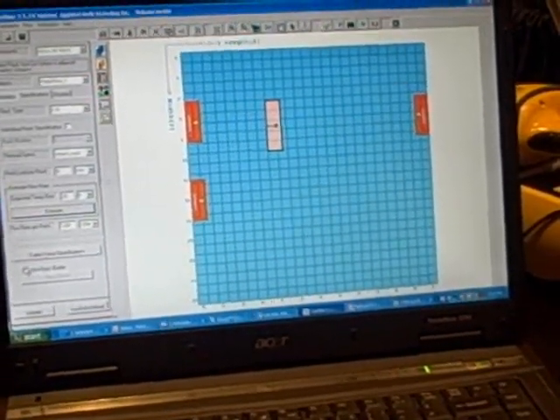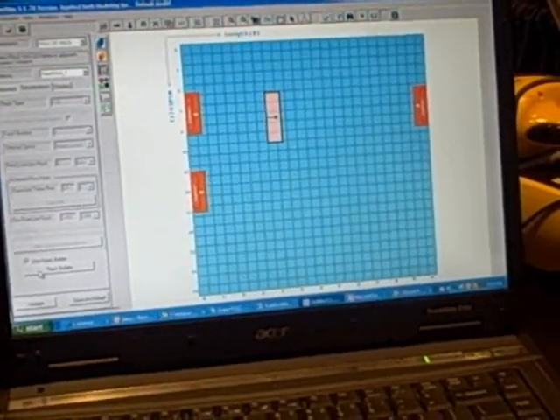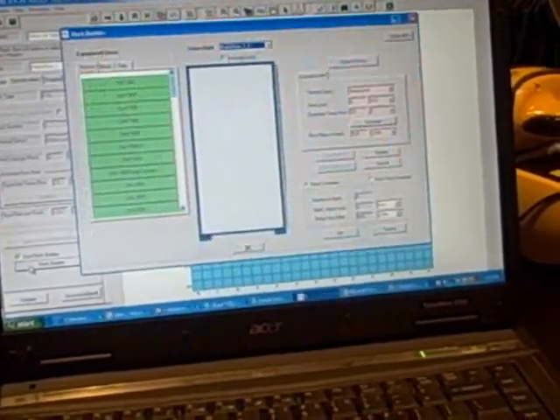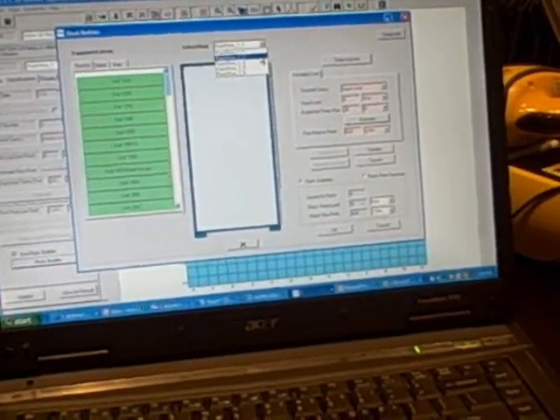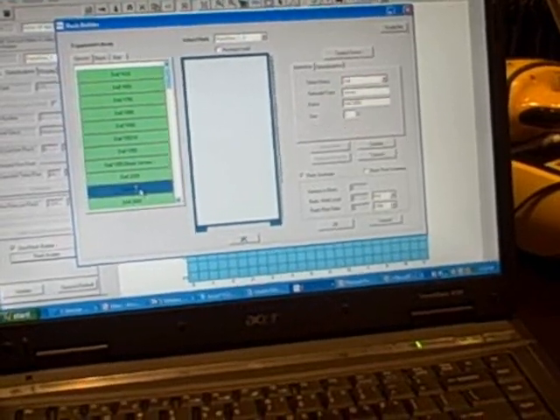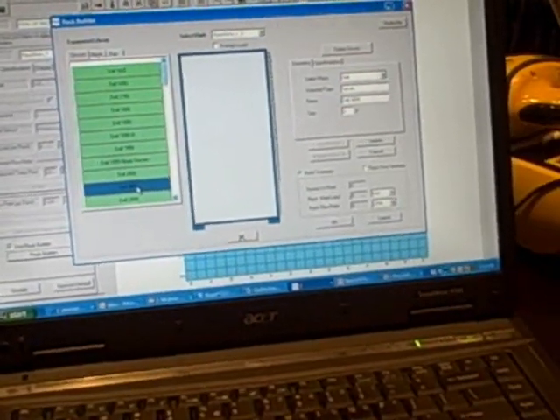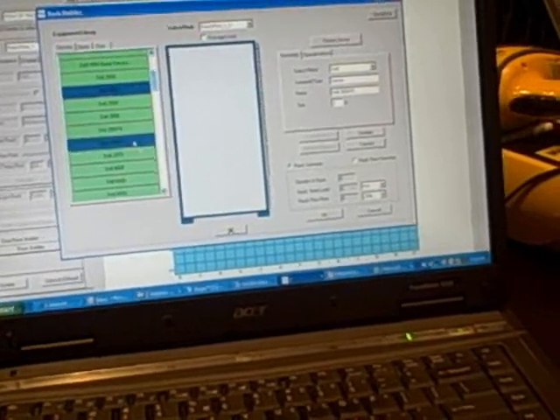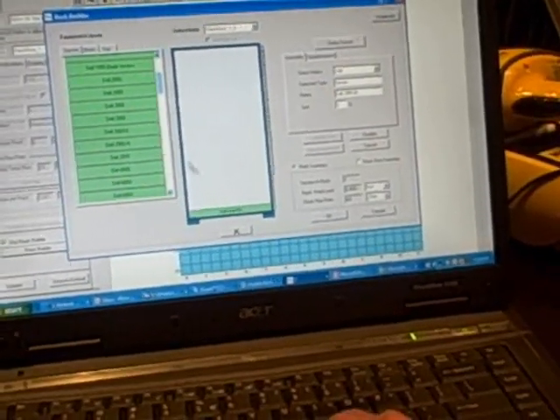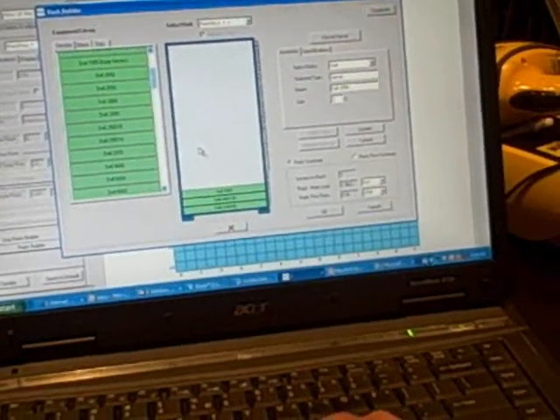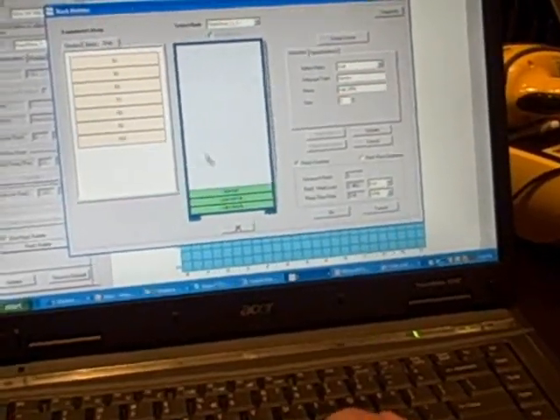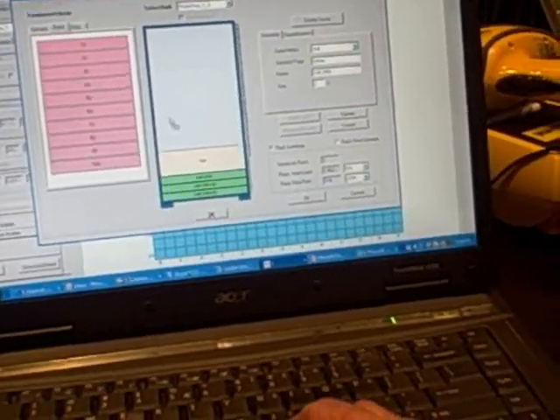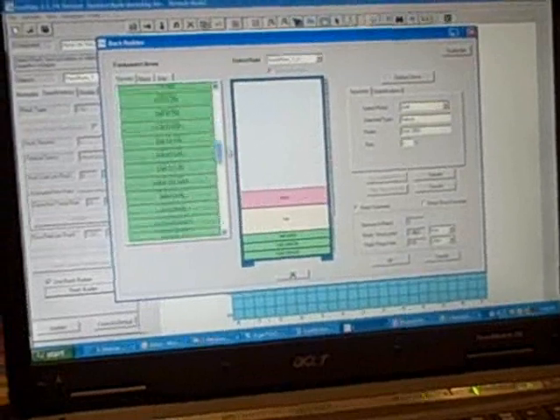But most recently in this release at 3.2 we've also added something called a rack builder tool. A rack builder tool allows you to open up the rack and to pick which rack in the row you want, click off average load and begin to look at specific servers. Here I have a library of Dells in place. And I can just simply take the Dell and move it into the rack by simply dragging and dropping them into place. I can also do gaps. I can model the effect of gaps or blanks in the rack as well. And any kind of server that's in my library.